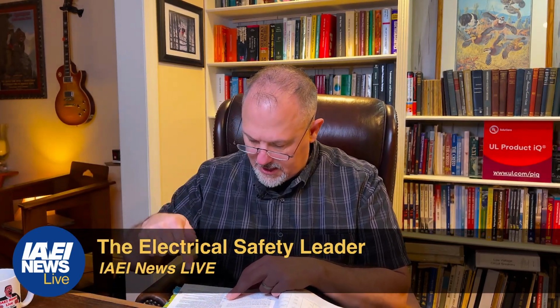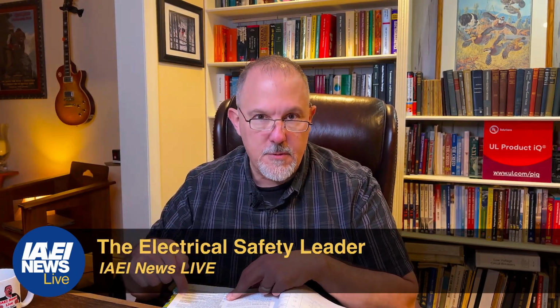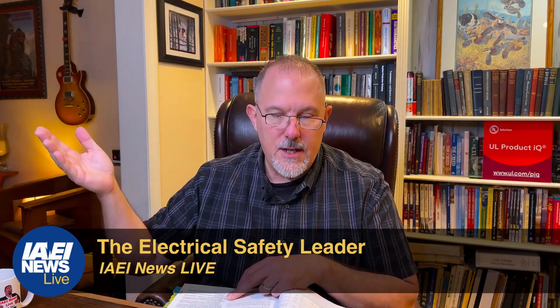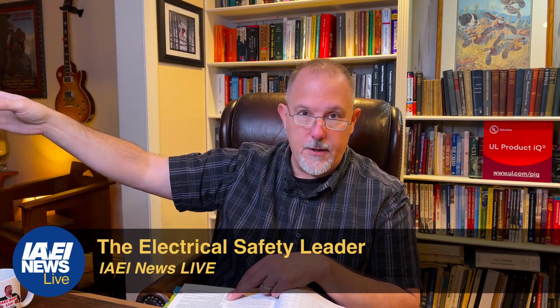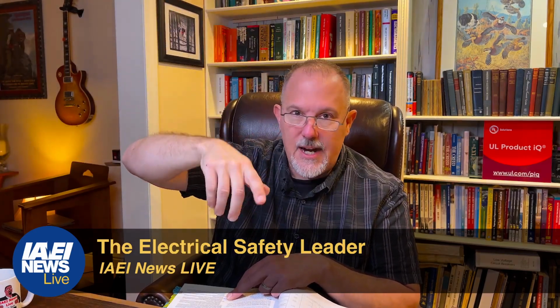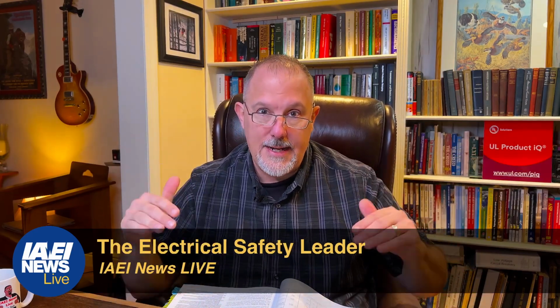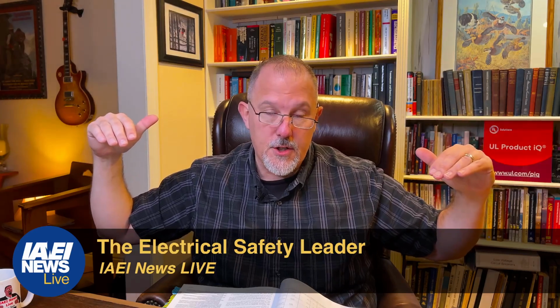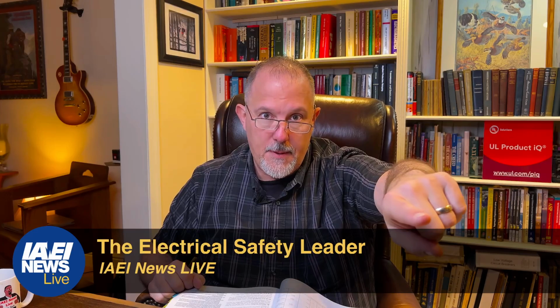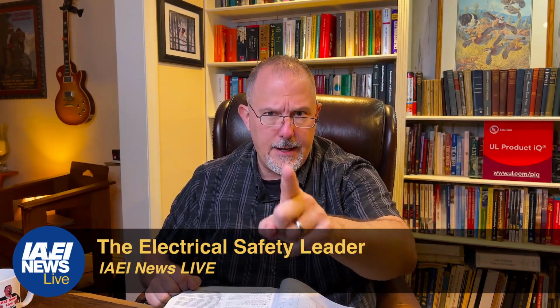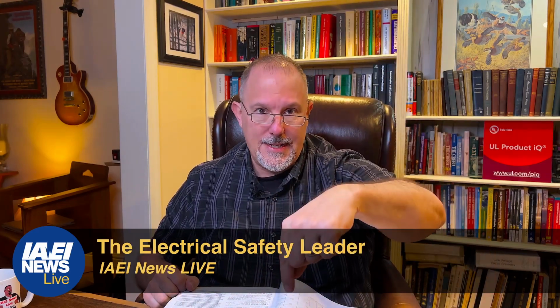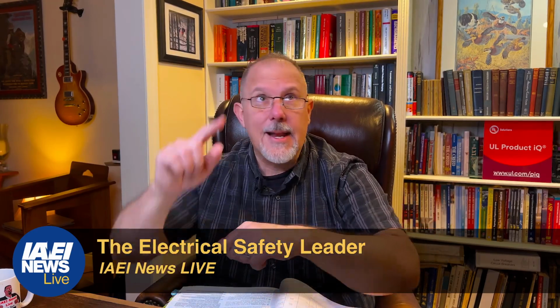Where the box enclosing the switch is accessible for the installation of an additional or replacement cable without removing finished material. So if you have a light switch that is very accessible, I would say maybe even my basement is very accessible because I have ceiling tile. I have drywall here, I have drywall behind me, but I've got ceiling tile and I have complete access. I put one receptacle over here, I put one receptacle over there. It was very easy to add a receptacle down here because I have complete access to the walls from the top. So all I have to do is remove some ceiling tile, run a wire from the panel board down, GFCI and AFCI protect that circuit at its source, and bring it down through the wall to my receptacle outlet. And I can staple along the whole way. The only thing I can't do is staple inside the wall, but I can fish wires in and get them to these locations.